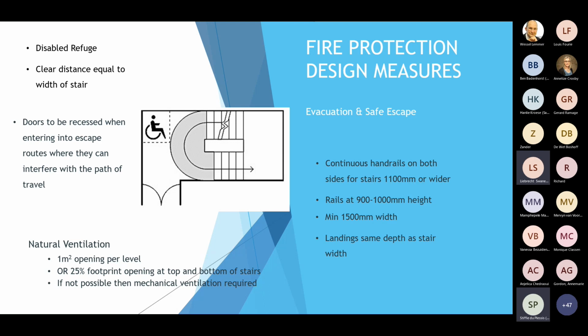and as I said, safe evacuation and escape, your escape routes normally can be rationalized based on the year of the building being erected. Obviously, my first question to each and every client is, listen, have we got previous designs that were signed off, or a previously issued fire clearance certificate? And that determines the width of your fire escape staircases. The latest regulation requires that each and every staircase will not be less than 1.5 meters in width.